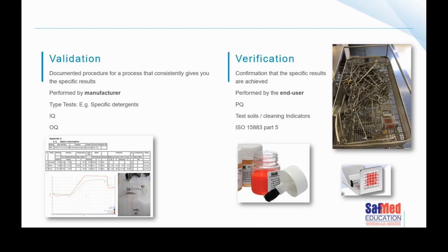Then there's verification — that's the end user, that's us in the CSSD. We have to confirm that what was supposed to happen did happen. For that, we also use test soils or cleaning indicators. The test soils and cleaning indicators we use must be manufactured in accordance with ISO 15883 or SANS 15883. Part 5 has not yet been adopted in South Africa. There are paint-on soils that are commercially available, or you can use cleaning indicators — quite a few suppliers provide these nowadays.